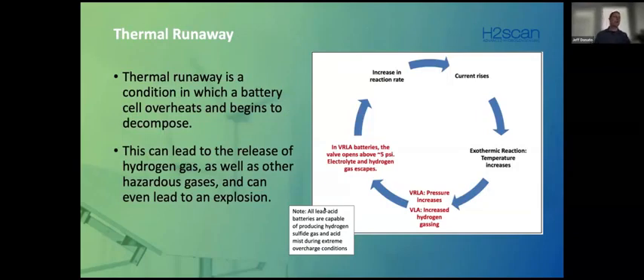Speaking of thermal runaway, it can actually happen in any of the battery types that we spoke of. It's mostly prevalent in valve-regulated batteries, and the reason is, as I mentioned before, the absorbed glass matting between the plates, which tends to trap heat inside of the battery. They're also a recombinant type of battery. However, in flooded batteries, you can achieve thermal runaway in overcharged conditions. Basically, this is an increase in current, which leads to an exothermic reaction, and the battery has a hard time cooling down.